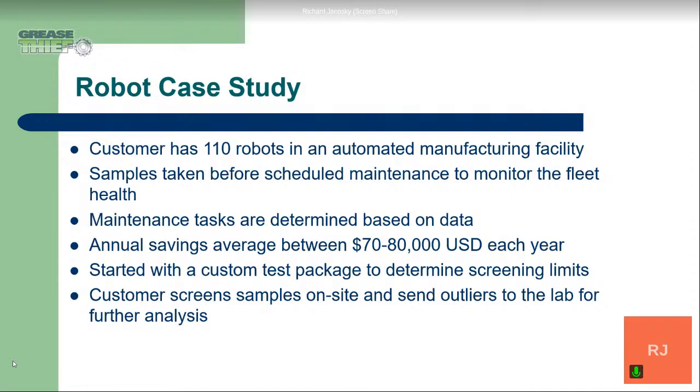That helped them be able to understand when they might need to catch a sample and send it to the laboratory. And there are still sometimes we get a sample where we do the full analysis and we're able to show with data that the grease is still effective and good to go, or that the grease does need replenished. But they're able to use that data to make the decision versus just trying to go off of a gut feeling or anything like that.